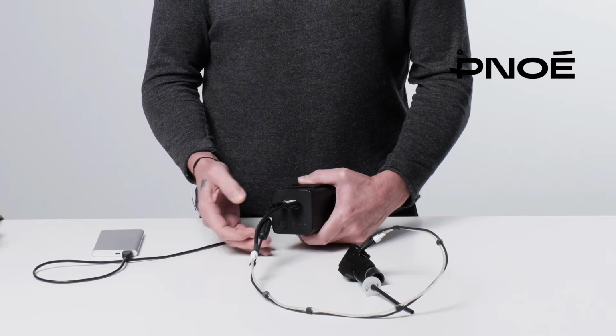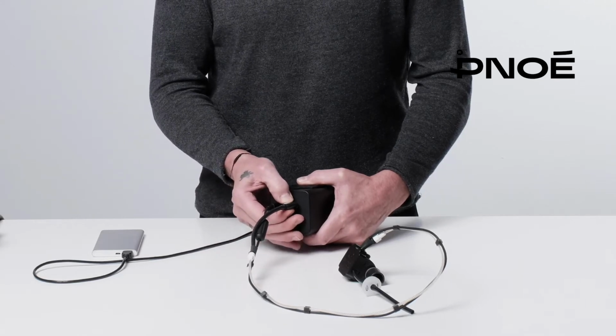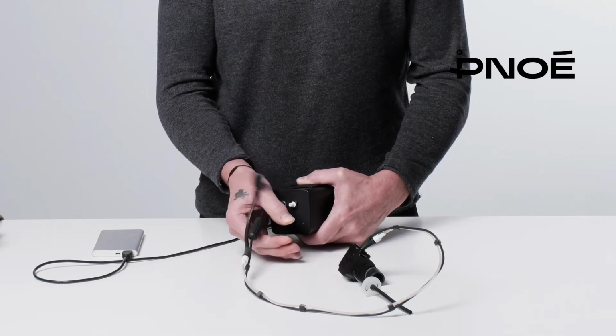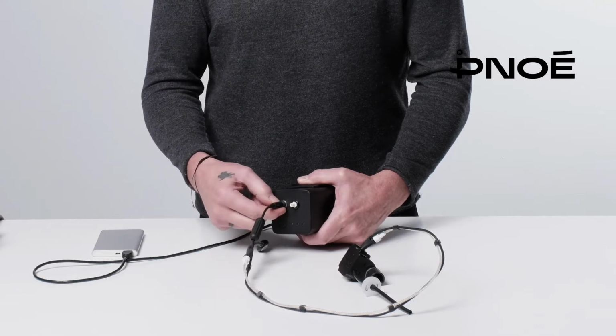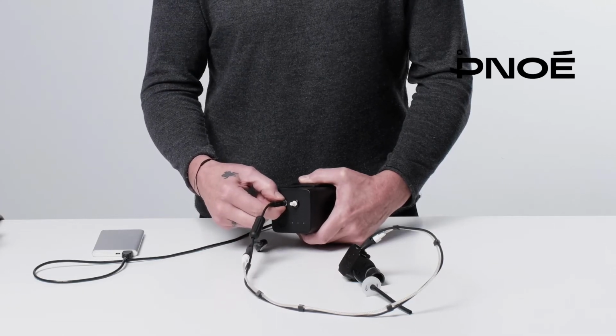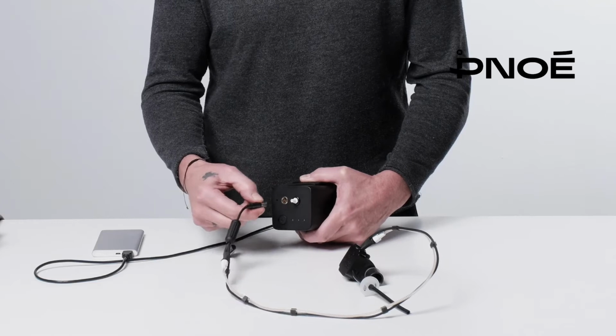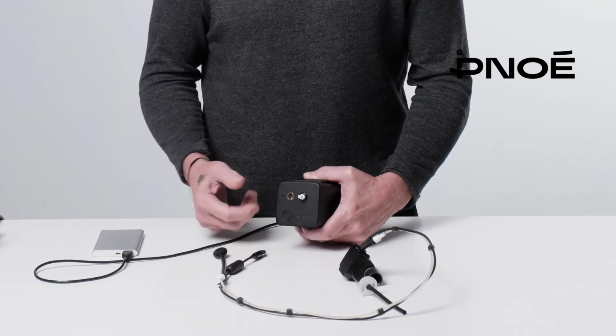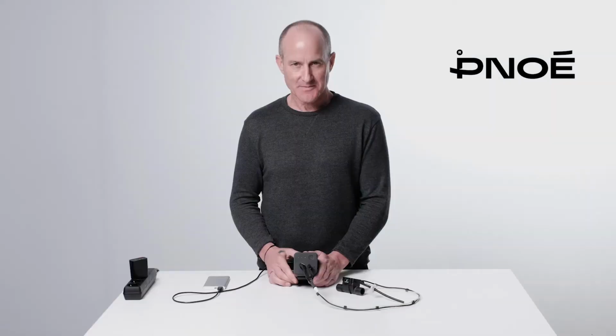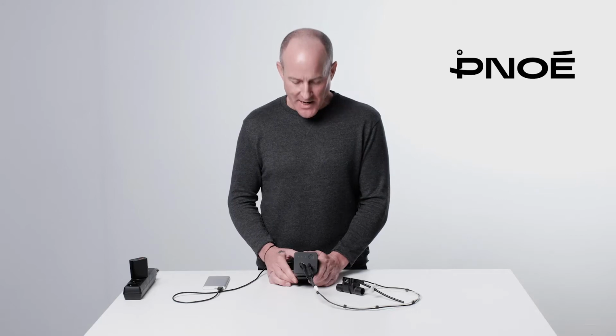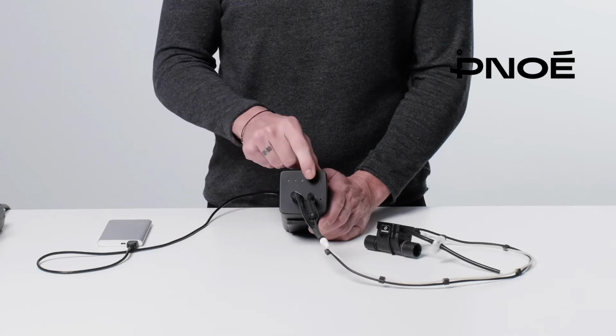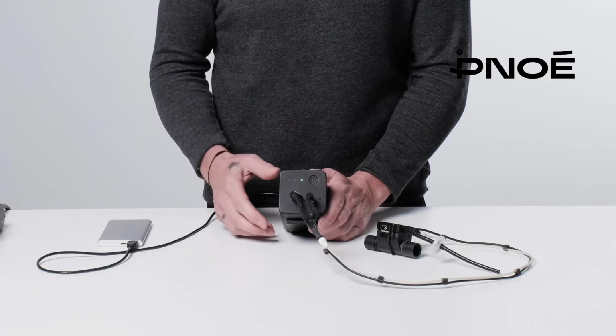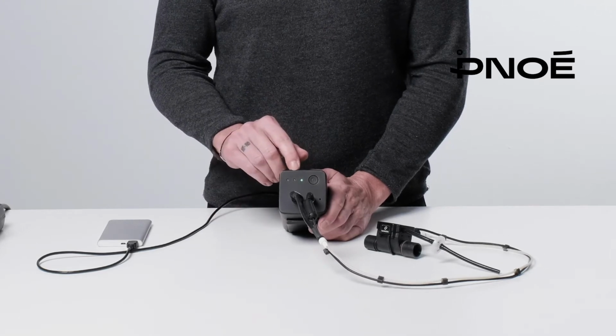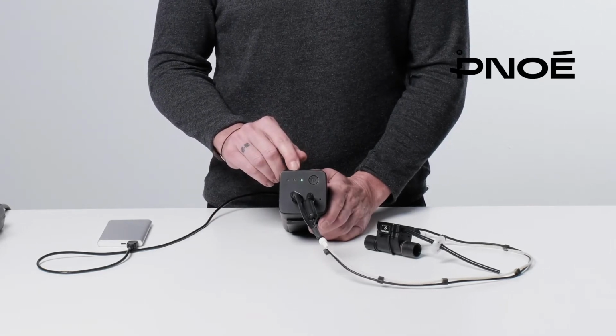To remove, you press the quick release, and then you can pull the sampling line off, and on the black button on the power cable, press the black button and pull, and you can pull the power cable from the device. Now your flow sensor is attached, you can restart your unit by pressing and releasing the power button. You'll see the solid green light and the flashing yellow light within 10 to 15 seconds.